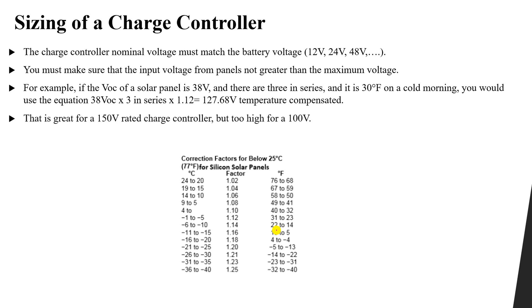For example, if you select a charge controller with a maximum PV input voltage of 150 volts, the calculated worst-case voltage of 127.68 volts is lower than 150 volts, so this charge controller can be used. However, if you use a charge controller rated at only 100 volts, that would create an overvoltage condition that may damage the controller. We must ensure the controller's rated maximum voltage is higher than the worst-case PV voltage.